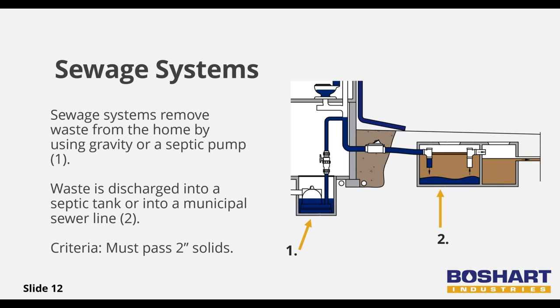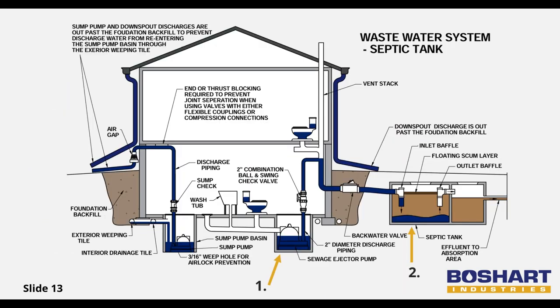Sewage systems can run by gravity, or if more practical, a sewage ejector pump will be needed to remove waste. The sewage ejector pump (arrow one) will eject waste to a septic tank or municipal sewer line (arrow two). Sewage check valves are often required for basements where sewage must be pumped up to a discharge line, and all sewage valves are required to handle a minimum of two inches for solid waste.